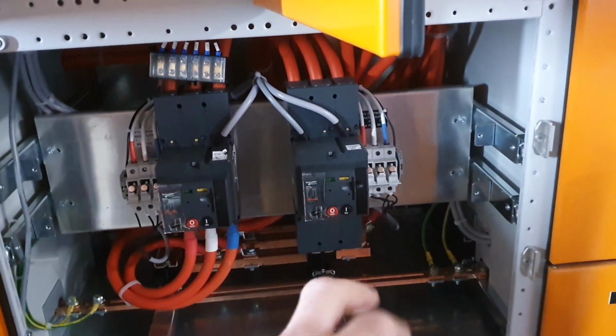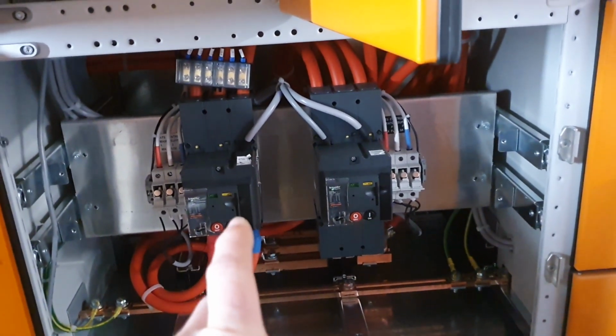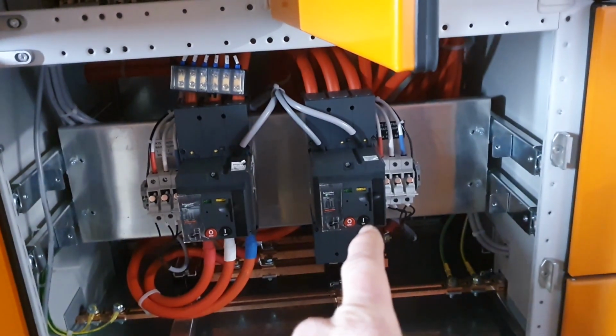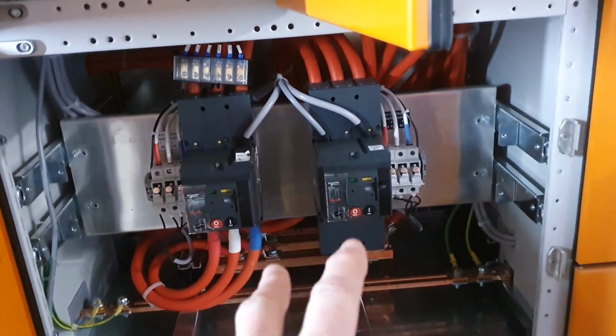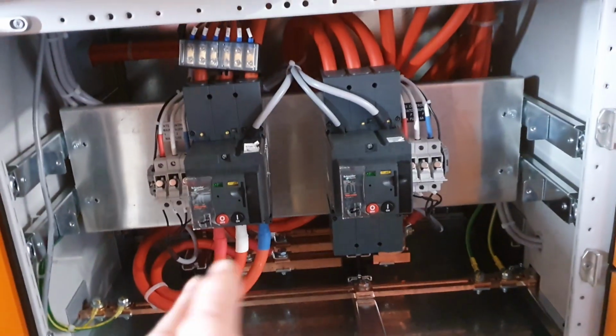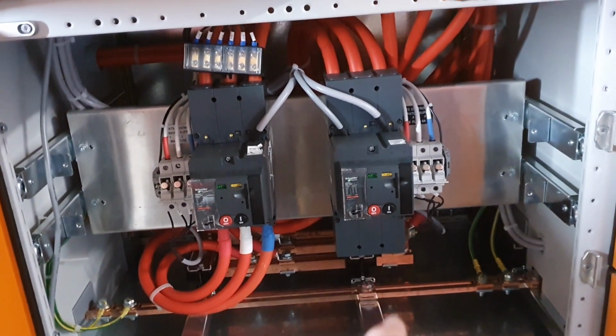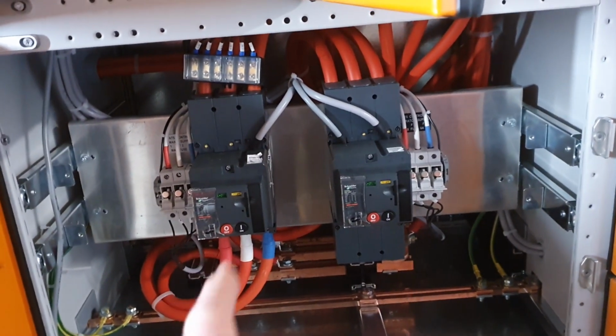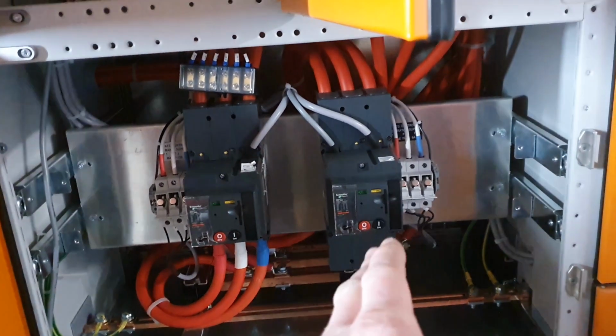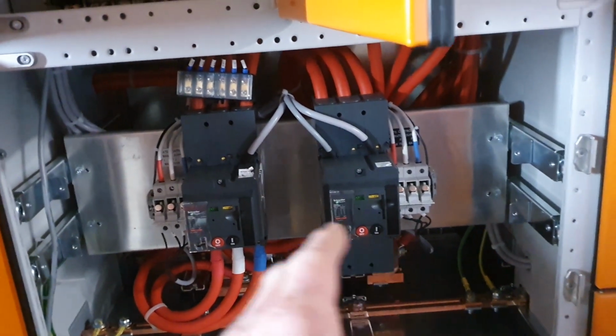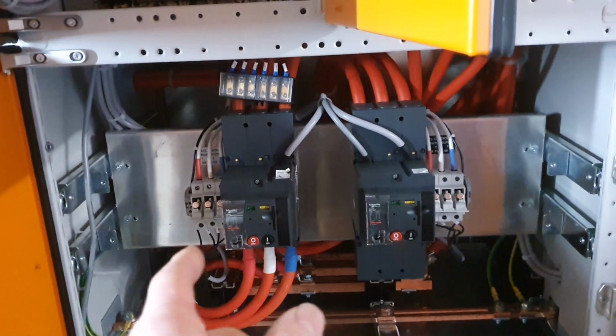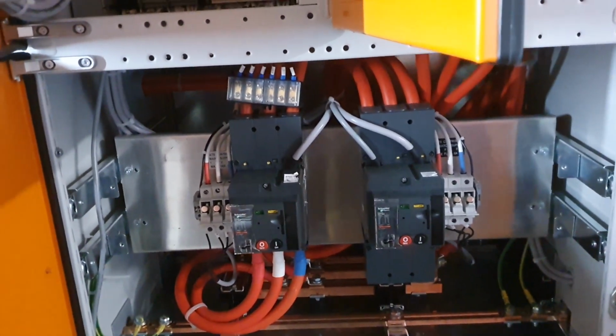So it's break-before-make in this case, because you can't obviously have - it's not so critical when you're swapping to the generator because the power's off, but when you're swapping back, when the power does come back on, this needs to turn off completely before that one turns on. Otherwise you could potentially have a phase-to-phase short, and this entire switchboard would probably blow up.